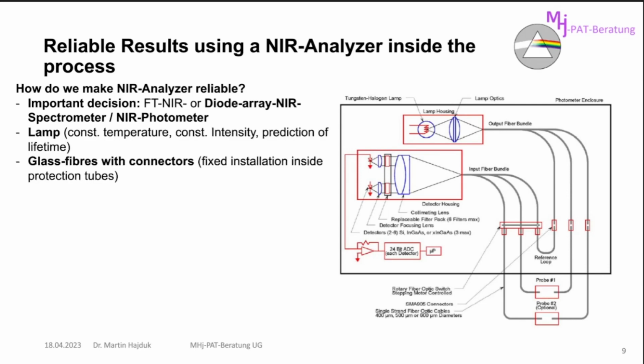So if we have a look at the lamp, the radiation of the lamp follows the Wien radiation law. That means it depends on the temperature of the filament. The light of the lamp depends on the temperature of the filament. So we need a very constant radiation: a constant temperature and also a constant intensity. Normally, we are doing this by controlling the current through the filament, and with the voltage which we need for this, we know something about the lifetime of the lamp.